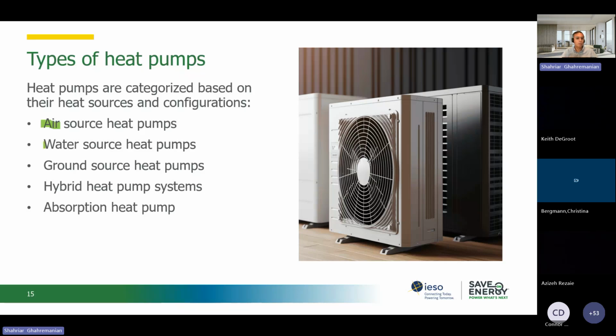The other one is a water source heat pump. I will have a couple of slides for these, because some people may not see them in application, but they exist. We use any water source that we have, like a pond or a lake, connect our heat pump, and take advantage of it. Or the ground source heat pump: digging the ground, with boreholes from 200 feet to 600 feet, and then we take advantage of the heat underground.